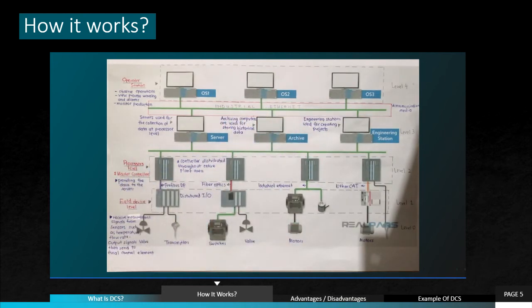Okay, now we're going to move to this level, which is the processor level. They have the master controller over here. Basically, in this DCS system, the controllers are distributed throughout the entire plant area. The function of these controllers is to provide the data to the server, which is here. Next we're going to continue with the field device level.